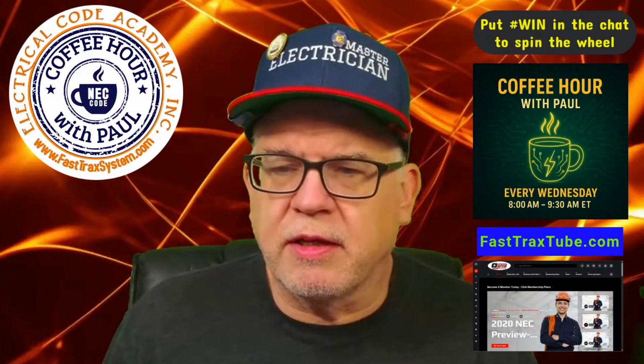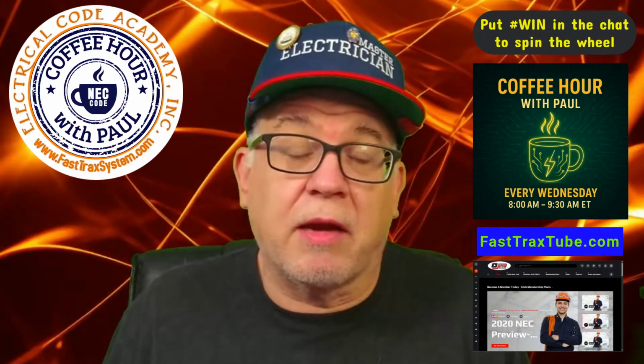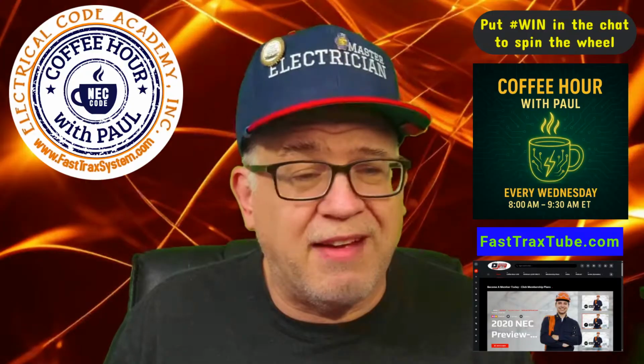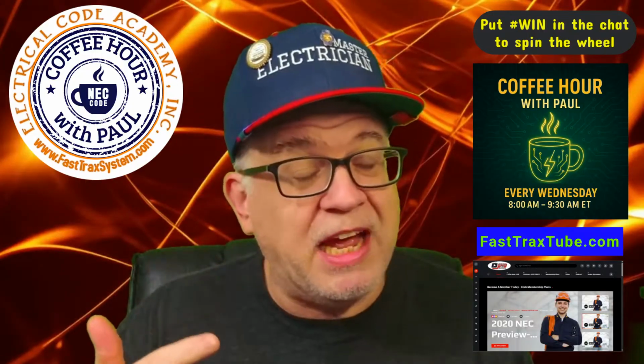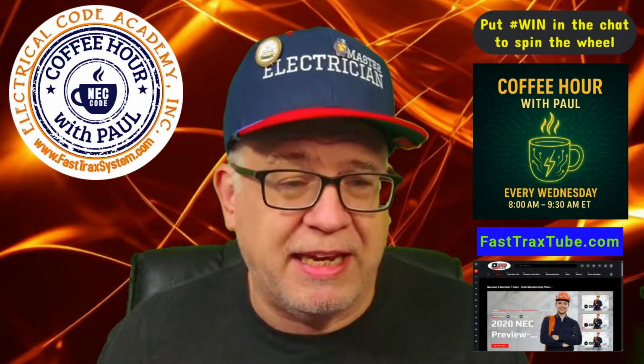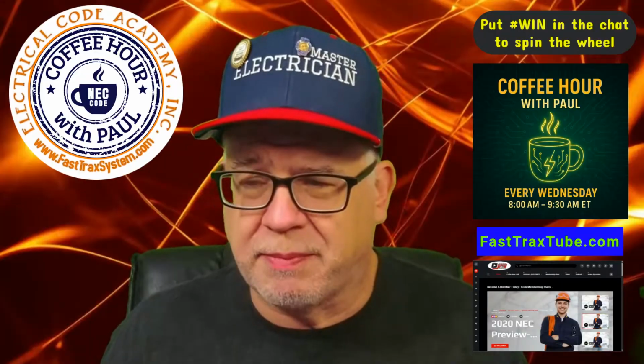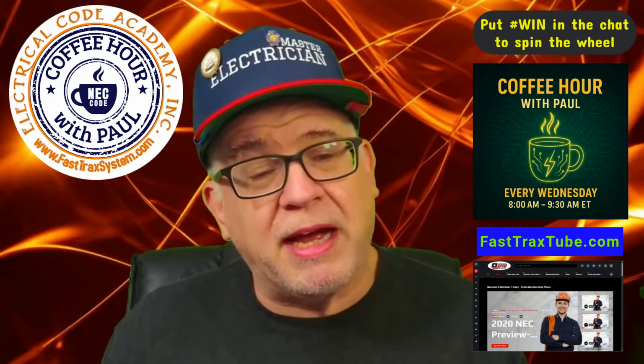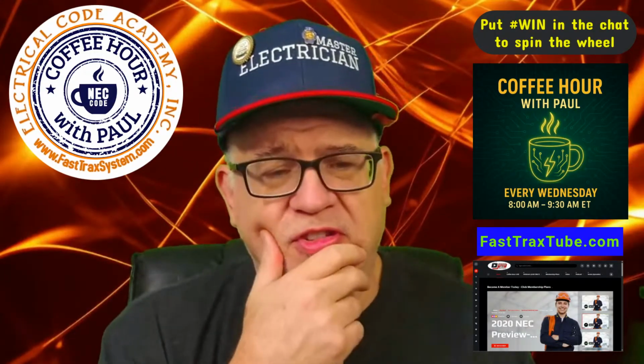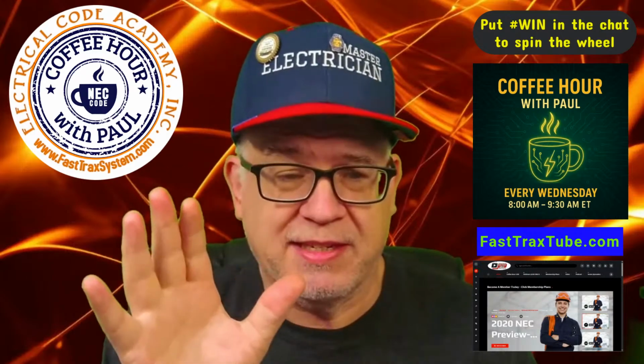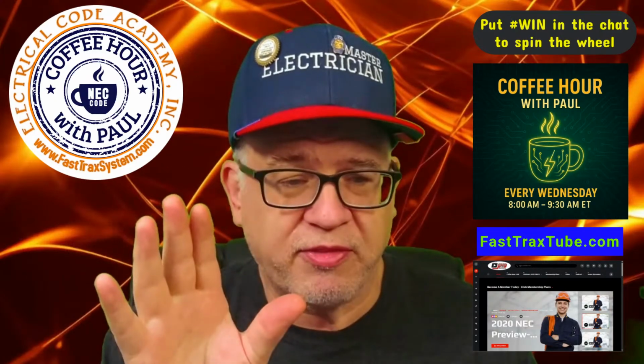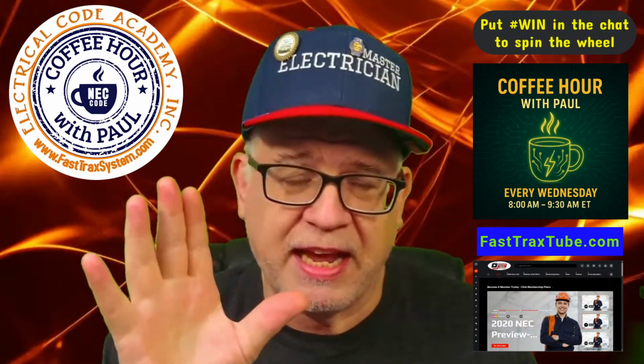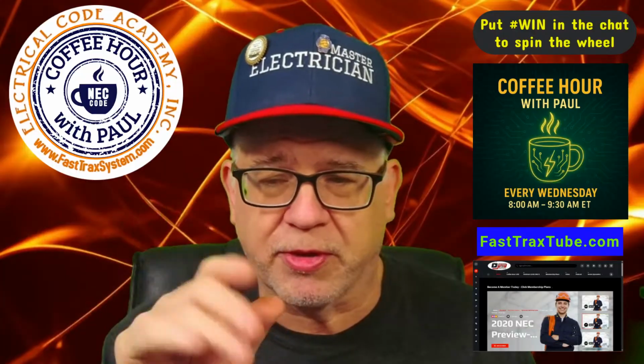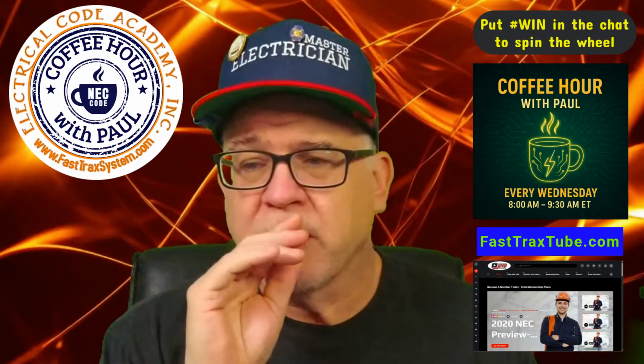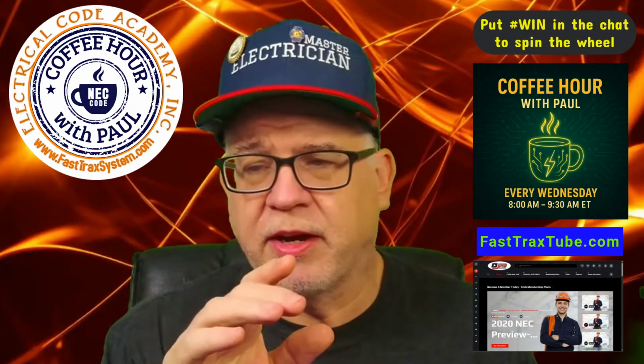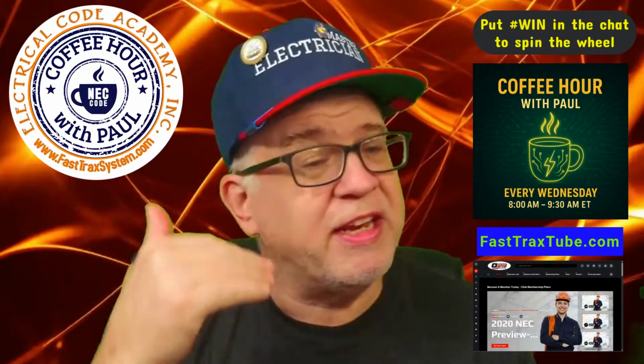What else? Limited energy systems. A lot of people get confused with limited energy. We have class 2, class 3, and now we have the class 4 fault managed system. Had a couple questions this weekend about fault managed. I'll remind you, fault managed systems are pretty neat - they're safer than GFCI, safer than an arc fault circuit interrupter. But they're unique - they're power over Ethernet to the next degree.